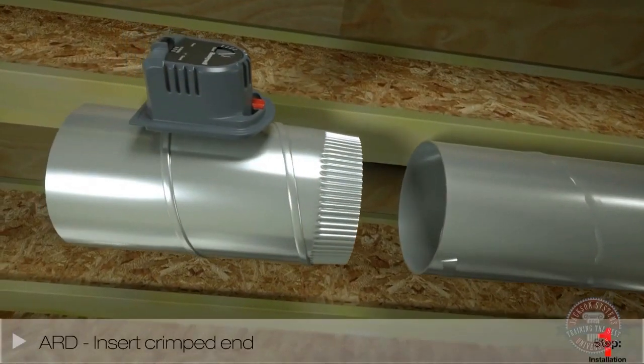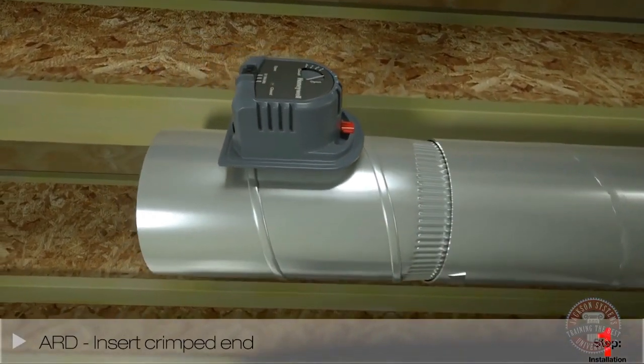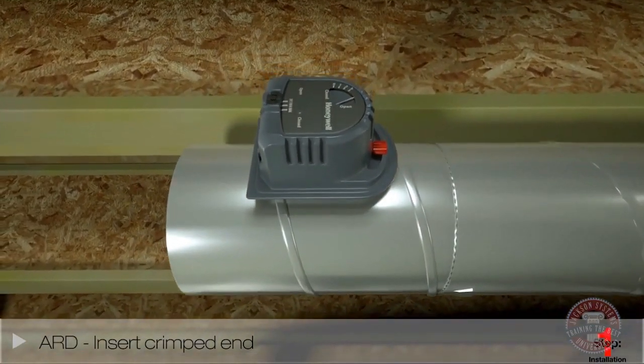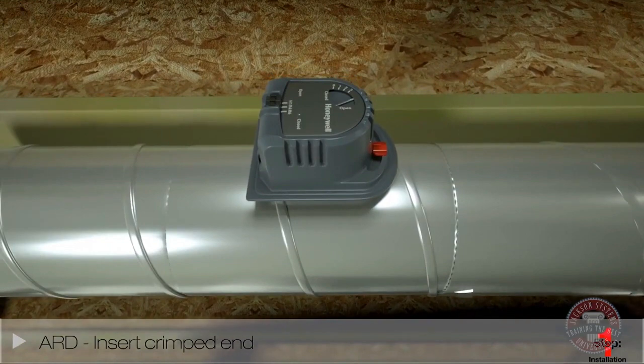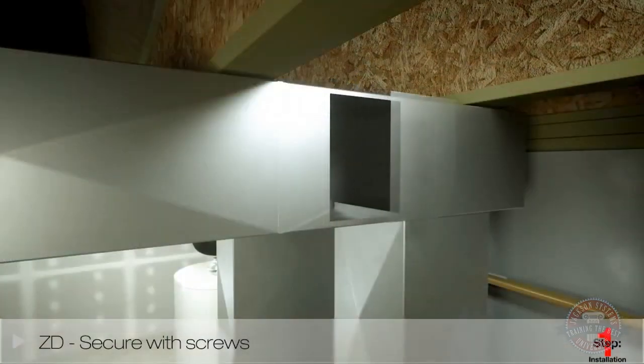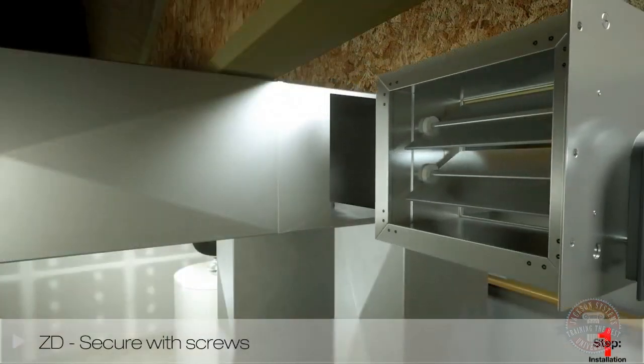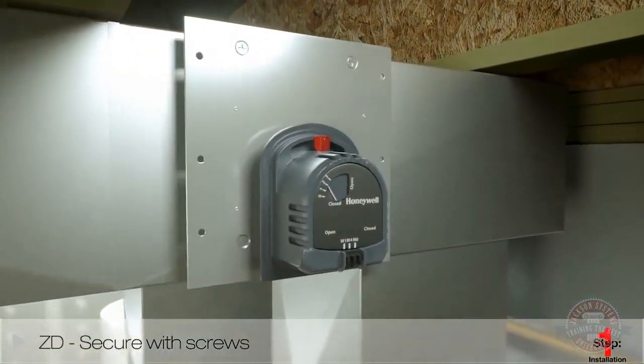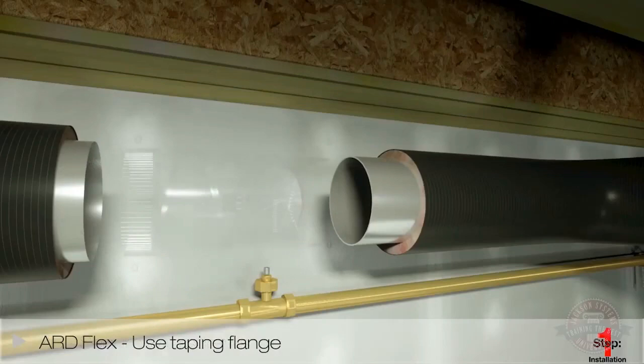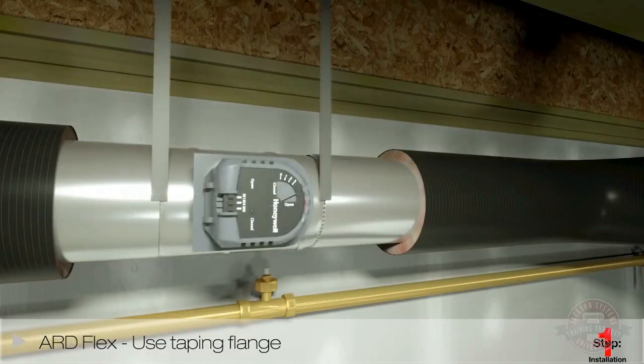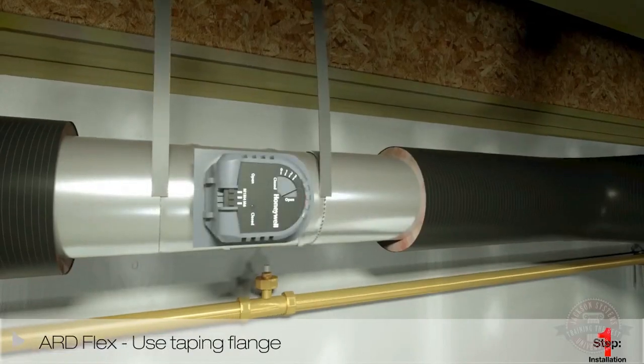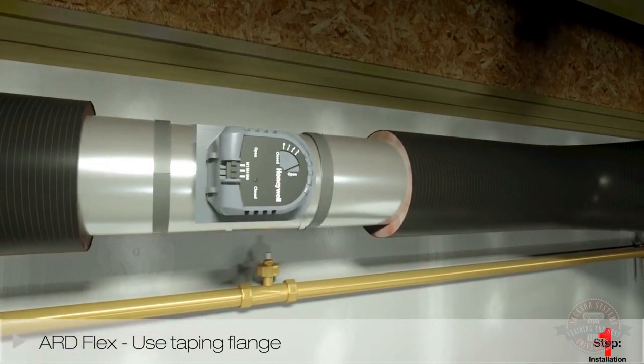For an automatic round damper, or ARD, insert the crimped end of the damper into the round ductwork. For a zoning damper, or ZD, slide the damper into the rectangular rigid duct and secure with screws. For an ARD damper with flex duct, mount it by attaching the flex duct over each side. Then slide the insulation under the actuator and use the taping flange for a proper seal.